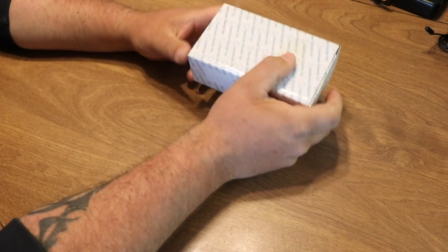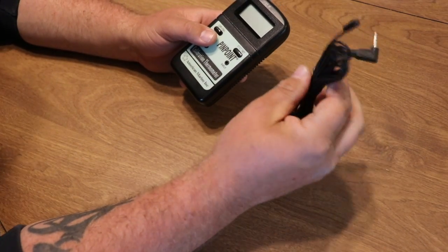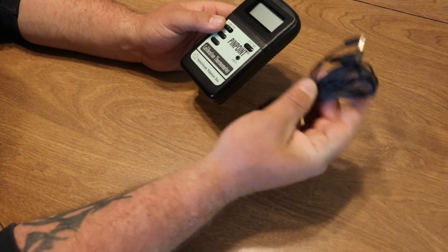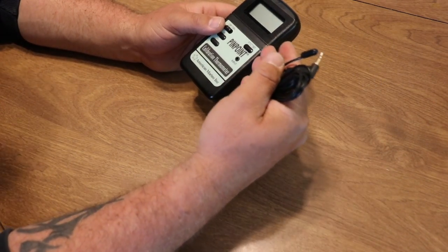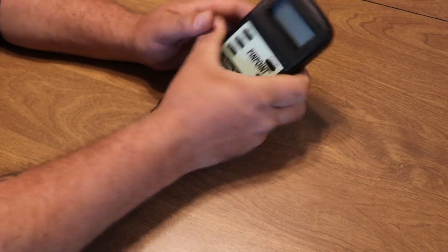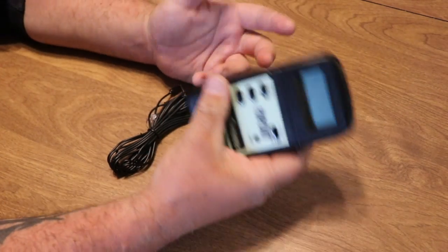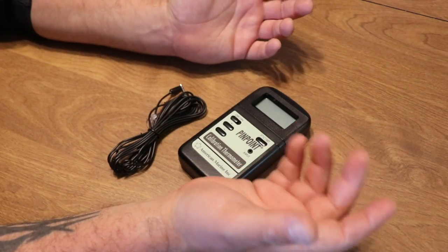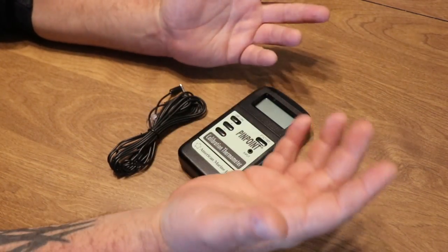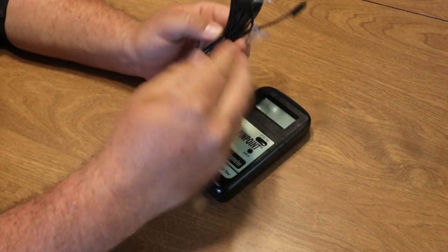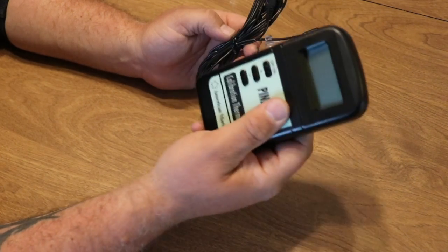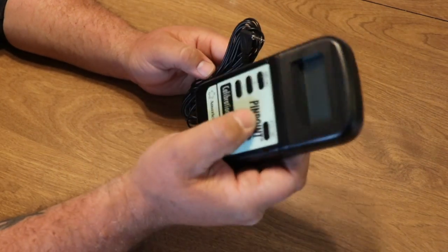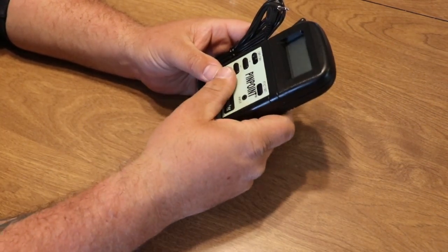Next up we have the PinPoint calibration thermometer. Now this one I'm very interested in, and kind of excited to be able to finally take a look at. The important thing to mention with the calibration thermometer is you have the ability to calibrate it, which is incredibly important. Now, the accuracy of this thermistor cable and its ability to communicate with this meter is incredibly accurate. Now, as far as calibrating your PinPoint calibration thermometer, it's pretty easy to do. All you need to do is take a glass of water and then put a lot of ice in it, create basically an ice bath, and then you take your probe, place it into the ice bath, and then if you're at Fahrenheit, it should be at 32 degrees. If you're at Celsius, it should be 0 degrees, and that will essentially help you calibrate your probes.